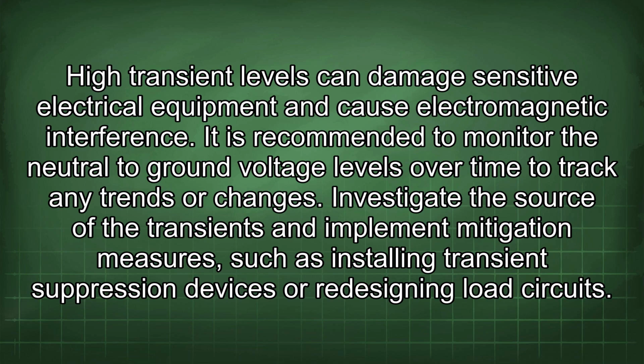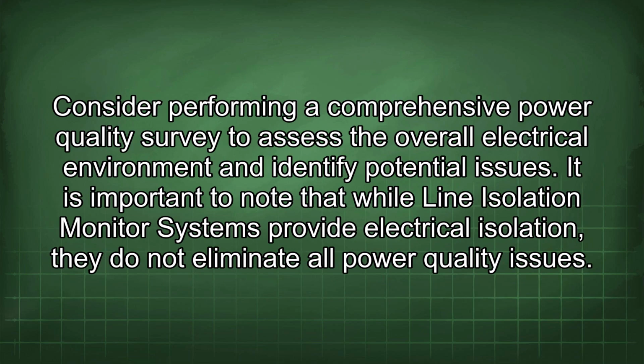It is recommended to monitor the neutral to ground voltage levels over time to track any trends or changes. Investigate the source of the transients and implement mitigation measures, such as installing transient suppression devices or redesigning load circuits. Consider performing a comprehensive power quality survey to assess the overall electrical environment and identify potential issues.